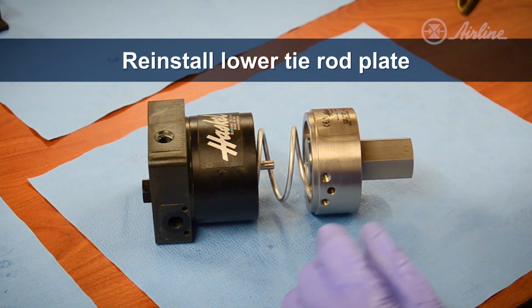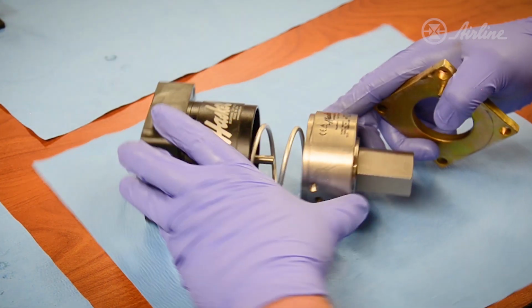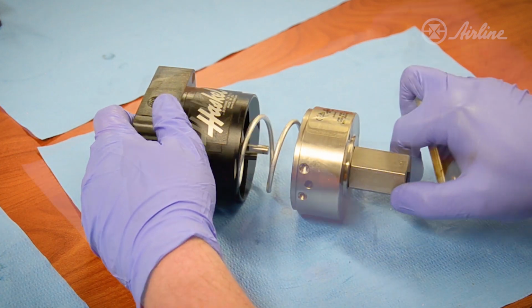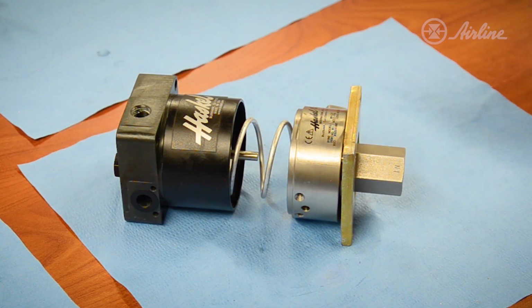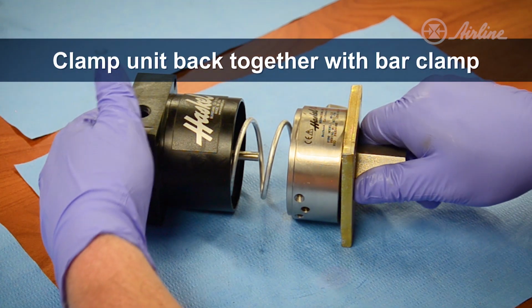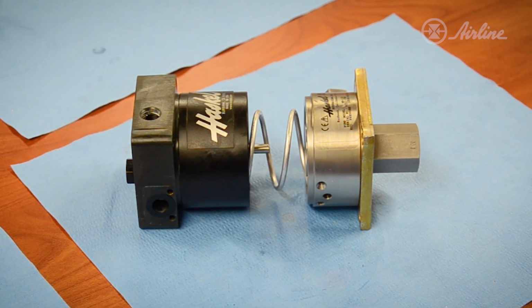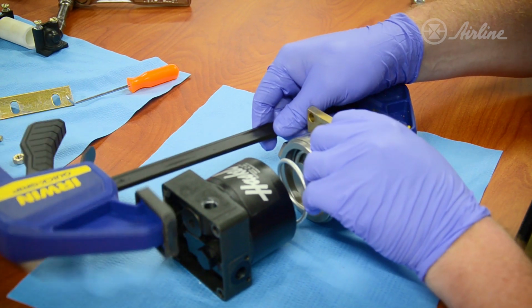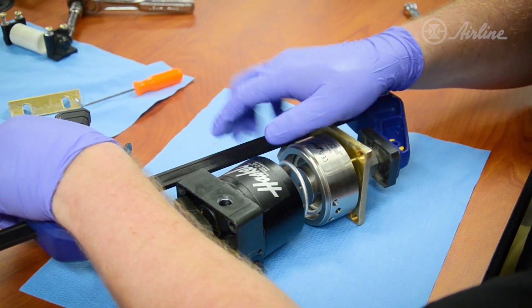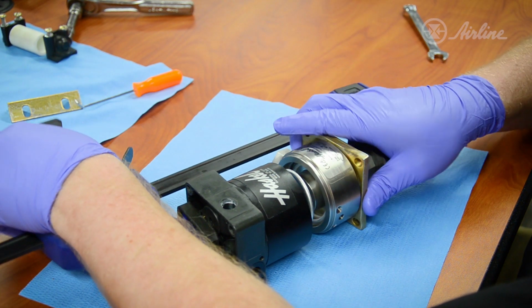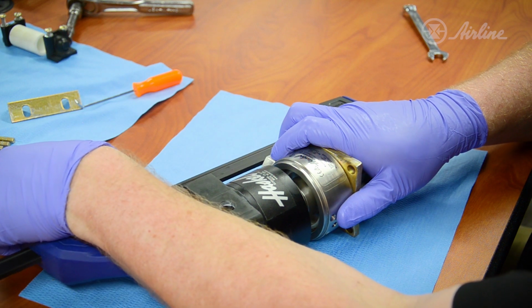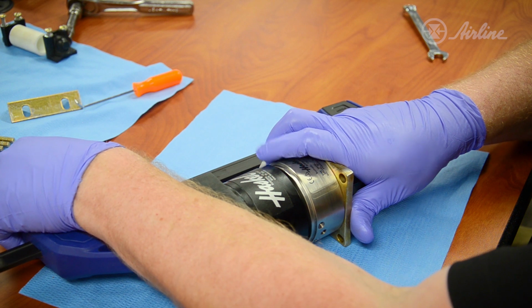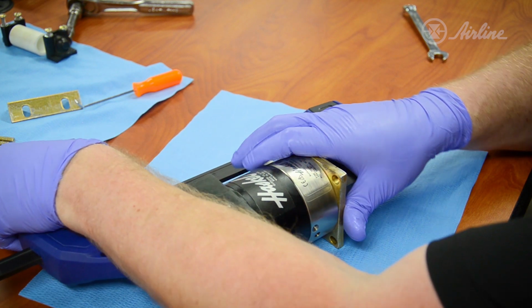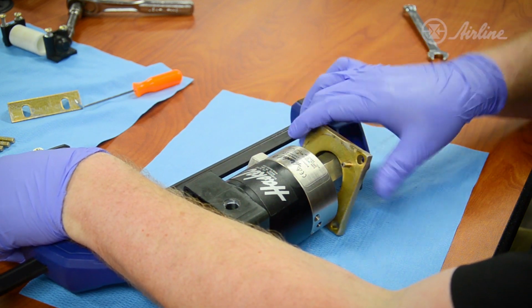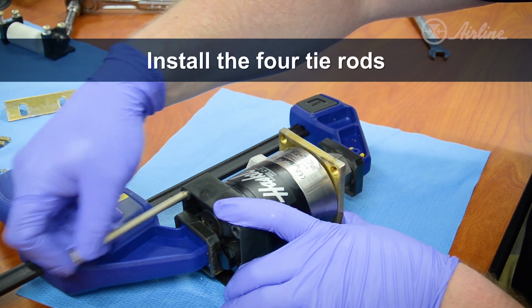So we need to remember to reinstall our lower tie rod plate, which has a pin that engages the pinhole in the pump head. Now we're ready to use our bar clamp to clamp this unit back together to be reassembled with the tie rods. So we will carefully line up our bar clamp with the two halves of the pump assembly and start putting tension on the assembly until the plunger enters the hole in the pump section. From here, we can continue to compress the pump assembly until both halves are mated together again and our match marks are aligned. Now we can assemble our tie rods, installing all four of them hand tight before removing the bar clamp.